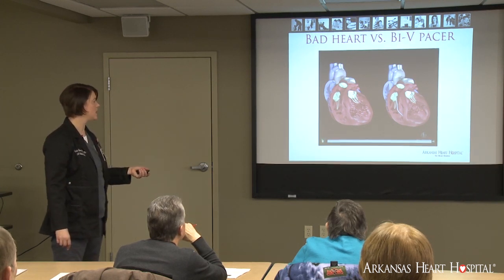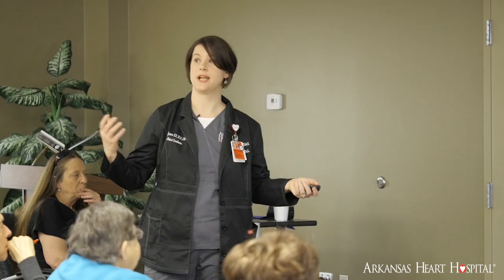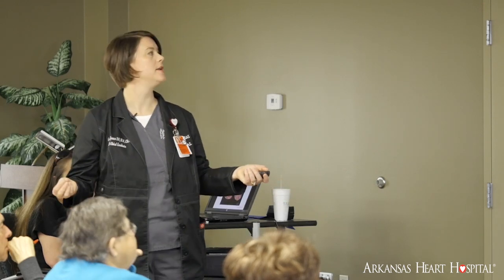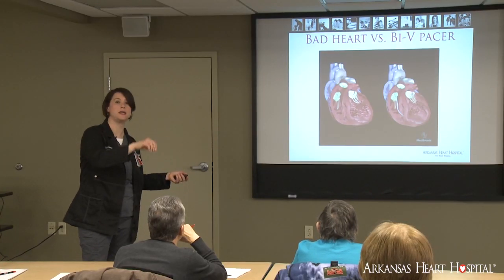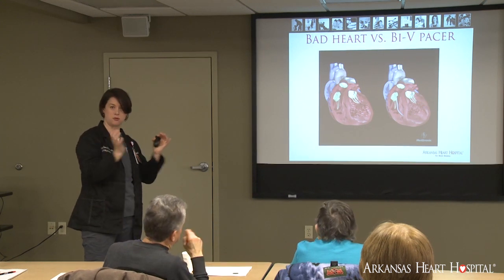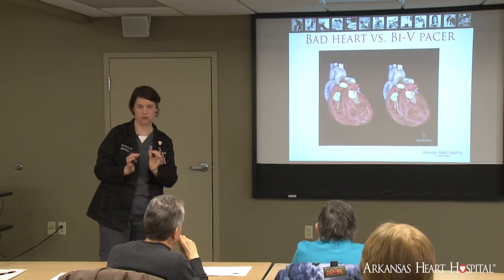But yeah, some of you in the hospital might have been told that you might have a defibrillator already, and your doctor's saying, I want to do a BiV upgrade, or put a third wire in. And lots of times we can just run the third wire in. That's going to go over on this side and pace both sides of the heart together. So what this BiV pacer does, it helps a mechanical problem, as opposed to an electrical problem.